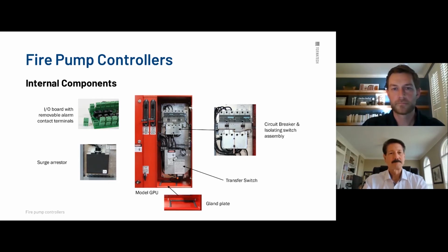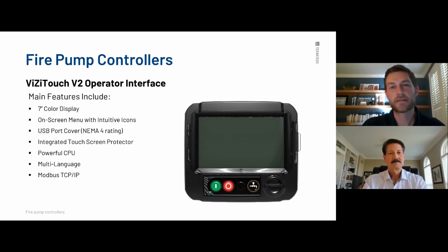Watertight hubs, remember? Yeah, watertight hubs. That's just to maintain the NEMA 2 enclosure as well. Like Marty mentioned, the NEMA 2 enclosure is drip proof. If you start cutting holes in it and you don't put a watertight hub on there, it's actually no longer going to be even NEMA 2. So especially if you've drilled through the top or the sides, if you don't use watertight, the NEMA 2 rating is not valid at that point either.